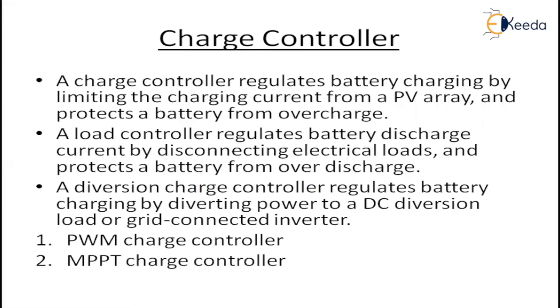Charge controllers regulate the battery charging by limiting the charging current from the PV array and protect the battery from overcharge. The first function is to protect the battery from overcharge from the PV array. Another function is as a load controller — it should not over-discharge the battery. These two functions correspond to two switches. If only these two switches are used, a simple controller is used, known as a PWM controller.